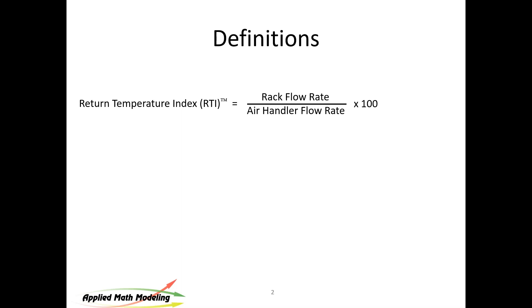I'm going to use English units today — I apologize to my international friends. I'll use CFM instead of cubic meters per second, and Fahrenheit as well. For altitude corrections, the CFM-per-kW figure shifts, but at sea level it's approximately 100 to 150 CFM per kW.